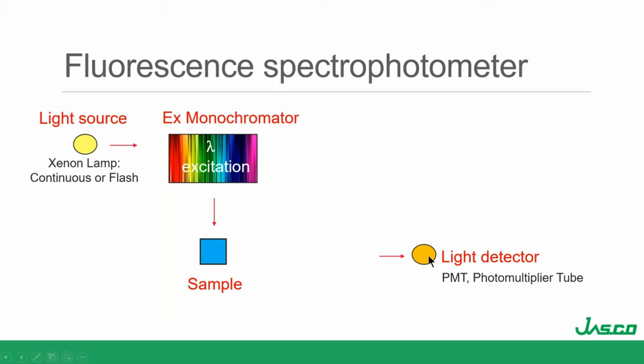We're missing something — it's detectors, especially photomultiplier tubes. They take a photon of light, turn it into an electron via the photoelectric effect, and then multiply it depending on what voltage you set. So I can go from one electron to a million electrons and really amplify the signal. However, these detectors are kind of dumb — a photon is a photon is a photon.